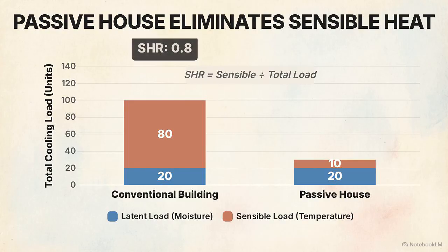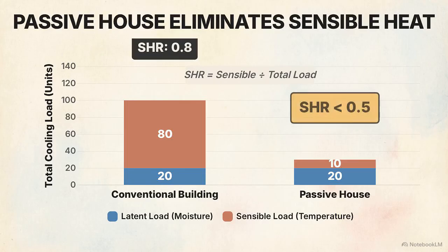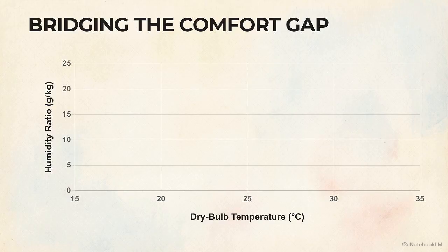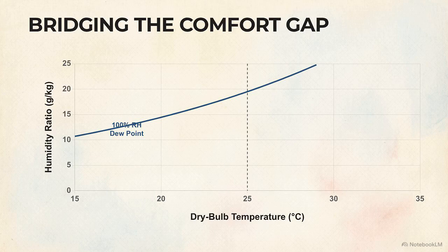Conventional buildings operate at 0.8 SHR. By stripping sensible heat, a passive house drops below 0.5. Inserting a conventional air conditioner into a low SHR building guarantees mechanical failure. The hardware is inherently designed to solve a 0.8 environment.